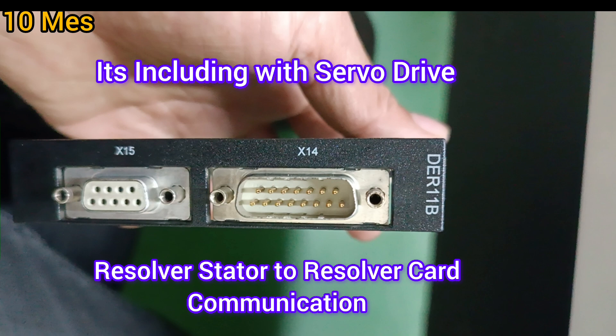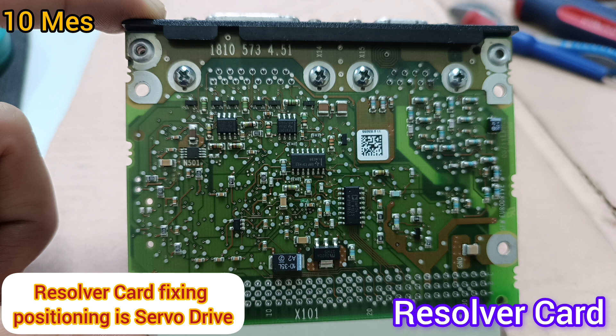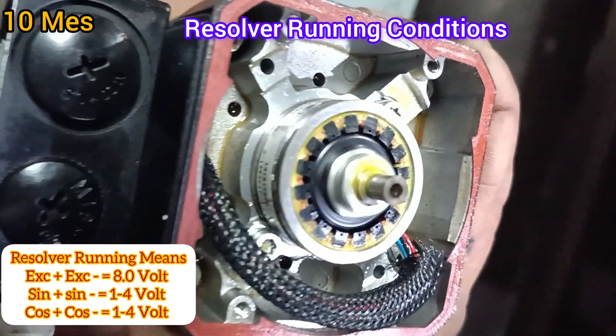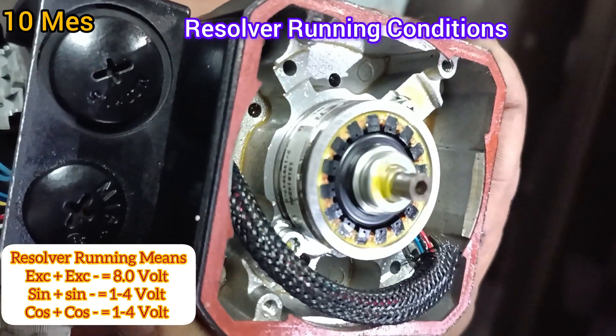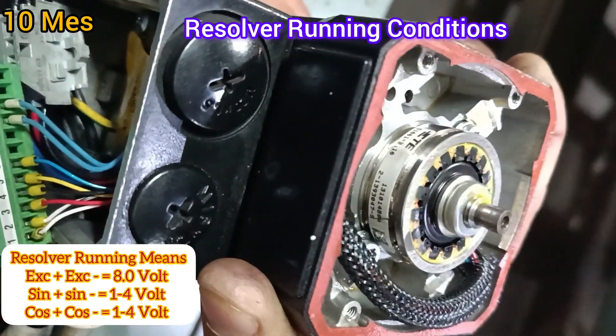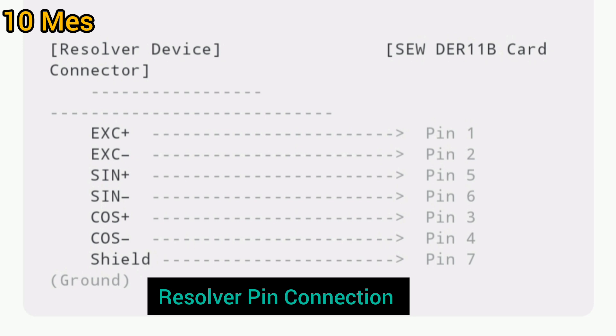The resolver has six cables to connect directly to the communication cable. This resolver card must be fixed in the servo drive. You can see the resolver running conditions: excitation plus and minus is equal to 8 volts, and sine plus and sine minus is 1 to 4 volts. This is the resolver pin connection diagram.